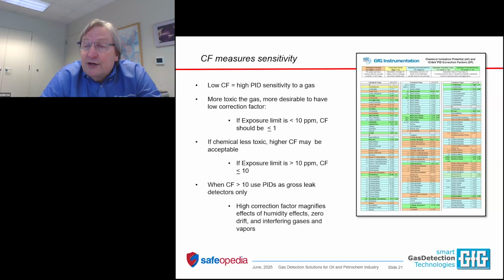The lower the correction factor, in other words, the less that you need to multiply the reading to come up with the true concentration, the higher the sensitivity the PID has to that gas. So a low correction factor is a good thing. That means the PID has higher sensitivity to that gas. The more toxic the gas, the more important it is to have a low correction factor. If the exposure limit is less than 10 parts per million, you should hopefully have a correction factor of less than or equal to 1. If the chemical is less toxic, you can have a higher correction factor. If the exposure limit is greater than 10, the correction factor could be up to 10.